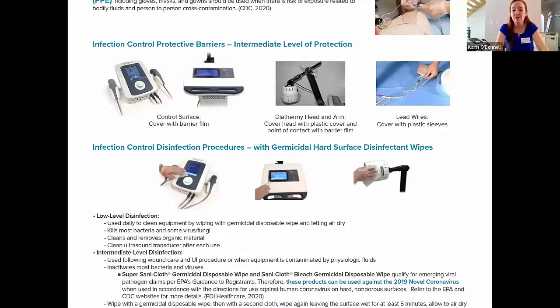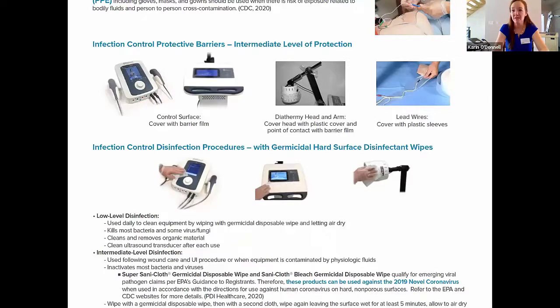The next level of disinfection is intermediate level. It's used following wound care, urinary incontinence protocols, or whenever the equipment is contaminated by physiologic fluids. Another instance you would use intermediate level disinfection is if the patient is on isolation — in other words, if you're putting on protective personal equipment such as a gown, gloves, face mask, etc., you would also want to protect your ACP equipment.